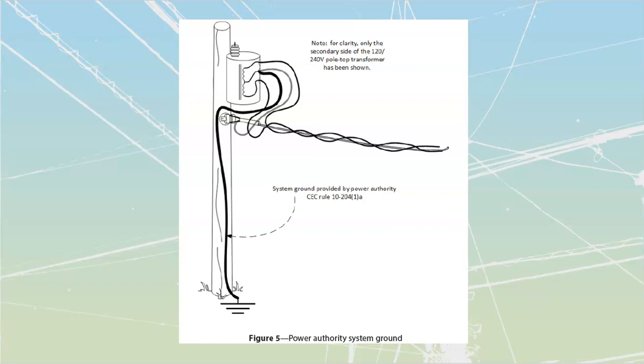And it is an incomplete drawing in that I don't have the primary of the transformer. That would be over here, attached to the high voltage lug. We don't have that drawn in. We're only showing the secondary side, but you can see it's a 120/240 type of winding, and I've got what we refer to as the identified conductor connected to the center part. You can see this thick cable over here would be BC Hydro's cable going down to the ground. It's going to be a system ground provided by them.